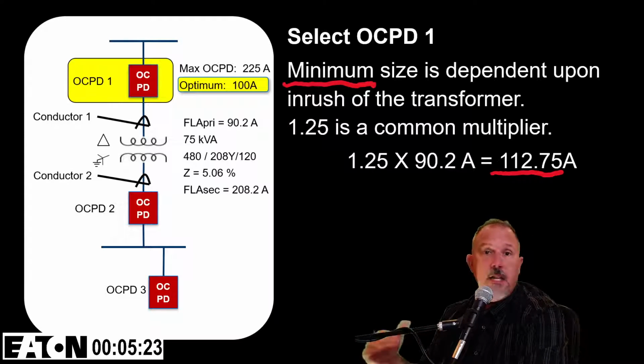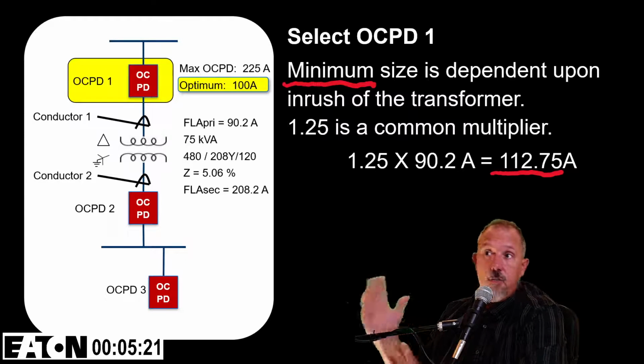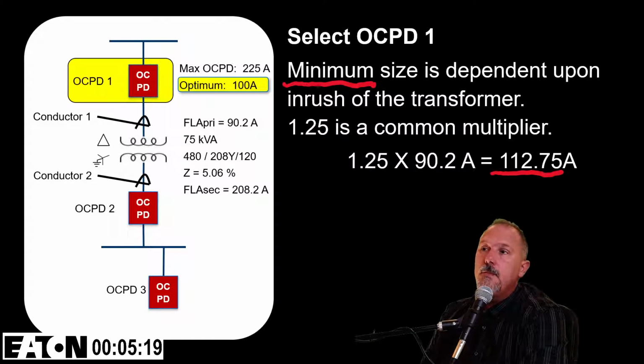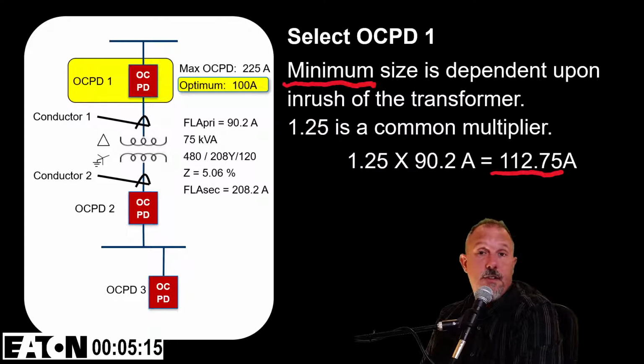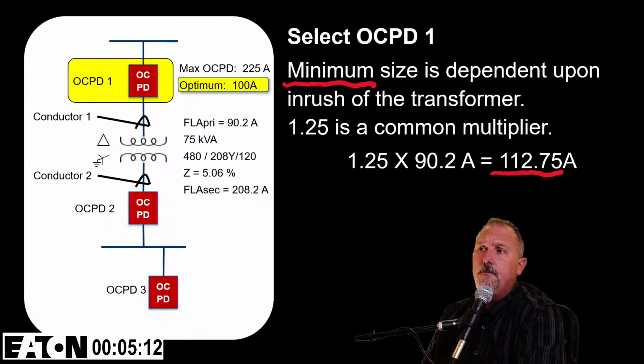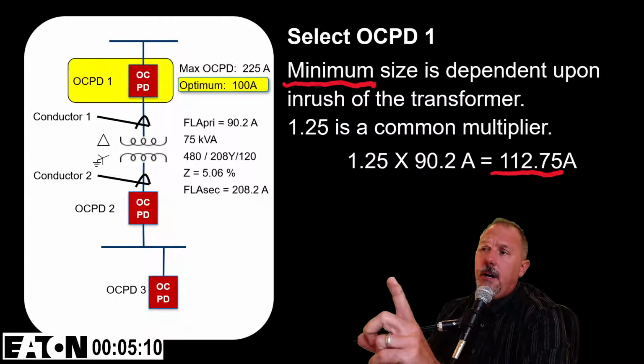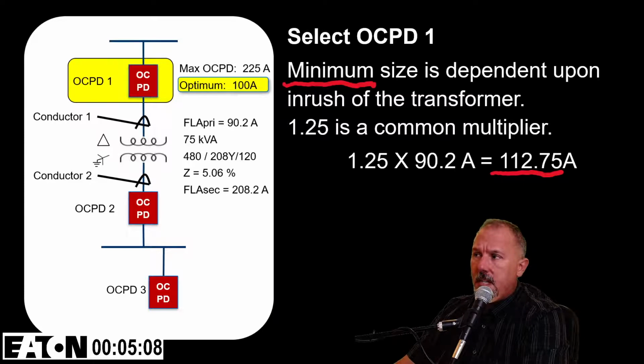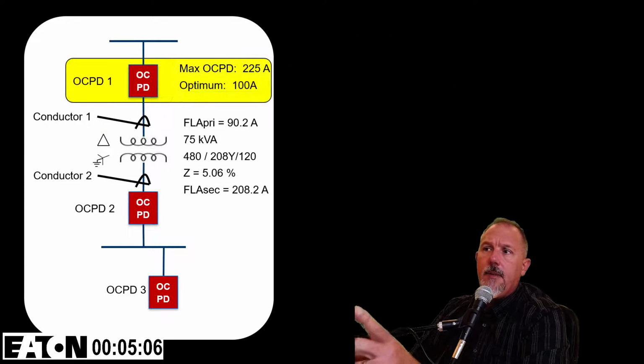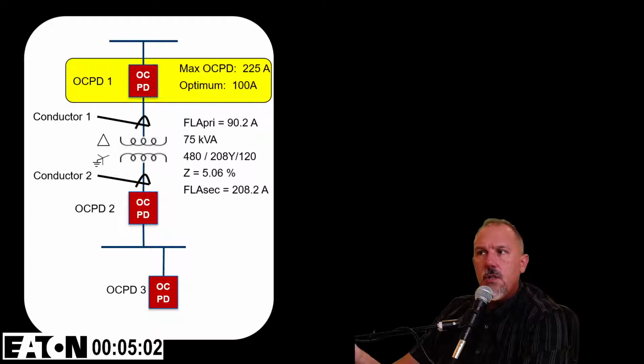I'm not driven by any specific number. I just can't go more than 225 amps. So I just selected 100 amps. I got 225, and I'm going to see if I can get 100 amps to work. So that's the overcurrent protective device number one, and I would say that's my range, anywhere from a 100 amp breaker or fuse to a 225 amp. And when you're at that 100 amp, you better be mindful of the inrush current, because we're going to look at some of the time current.